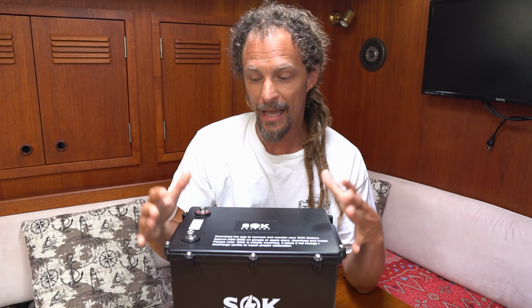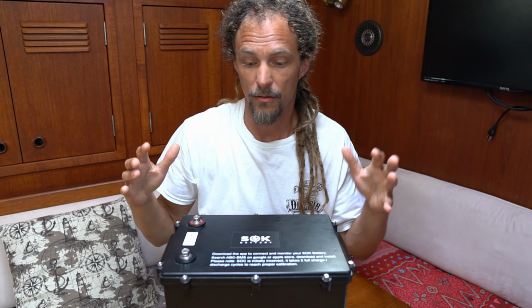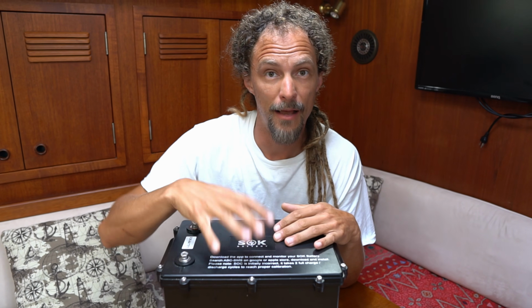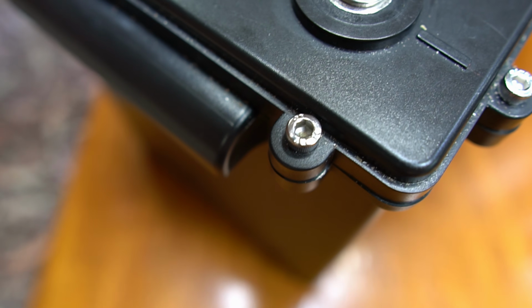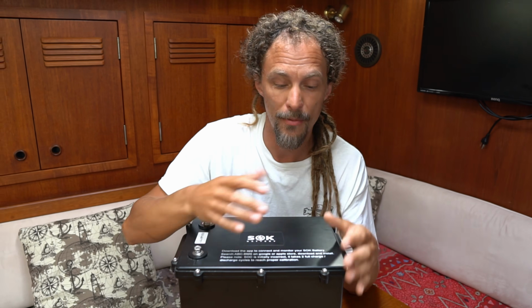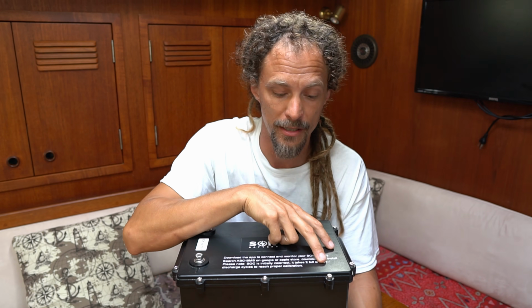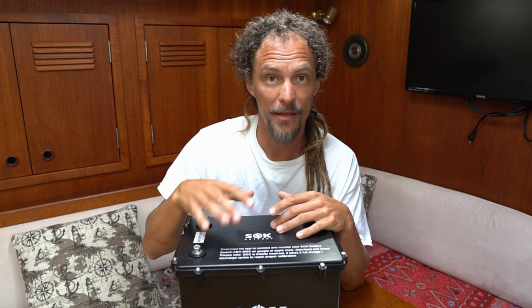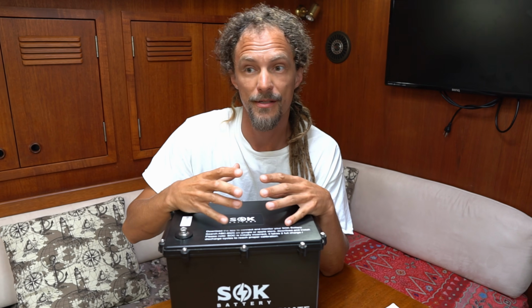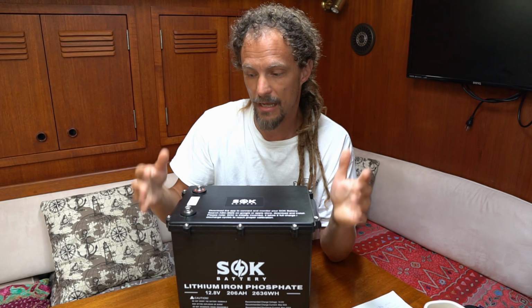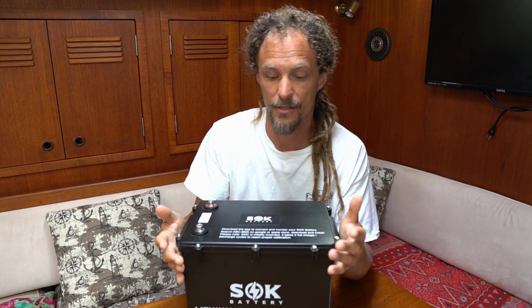But my absolute favorite feature: all you have to do to service anything that goes wrong in this battery is remove the 10 little Allen key bolts. The top comes off, and then you can swap out the BMS or swap out a cell, because they're bolted on, not welded like a lot of manufacturers do. So if you have a problem with anything internally, you can just get a replacement part and have your battery up and running again, which is huge.